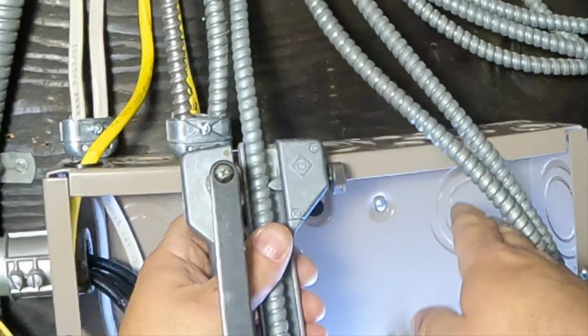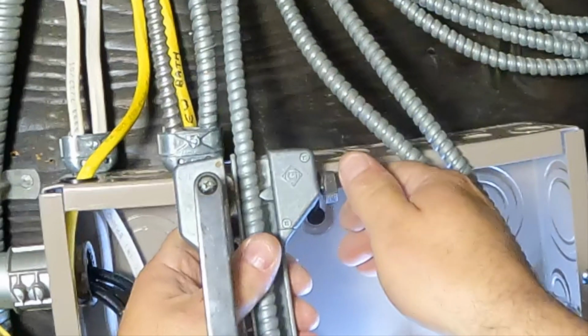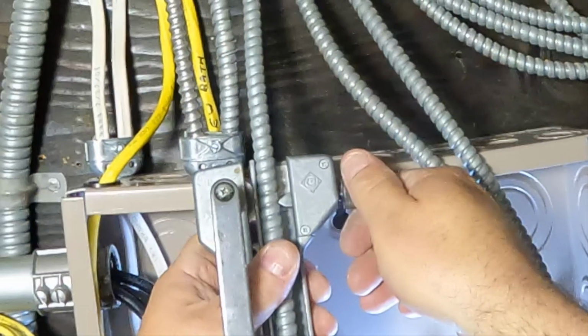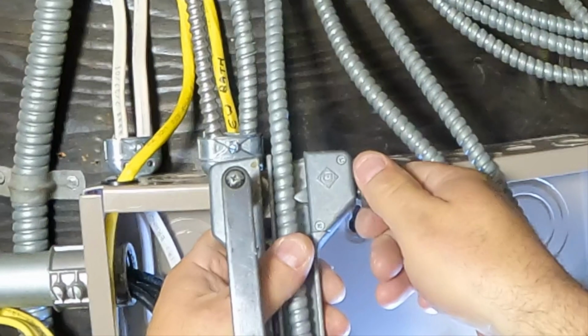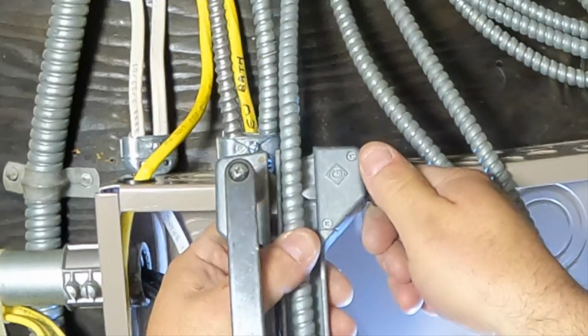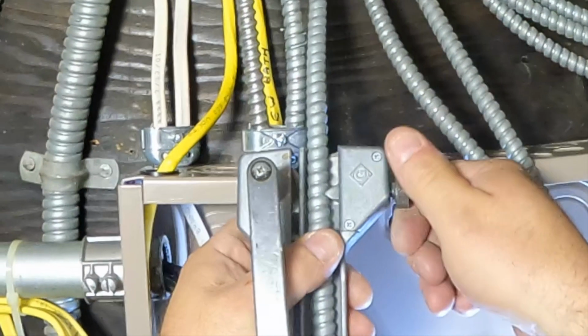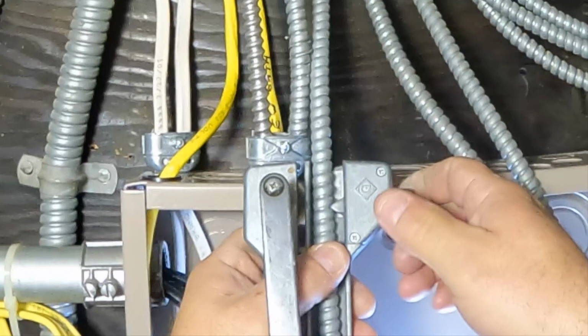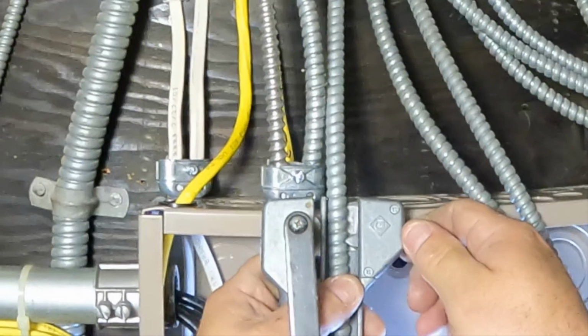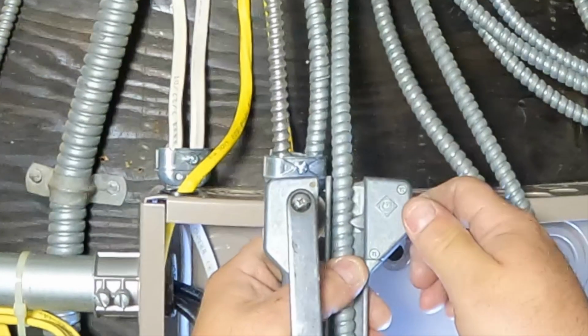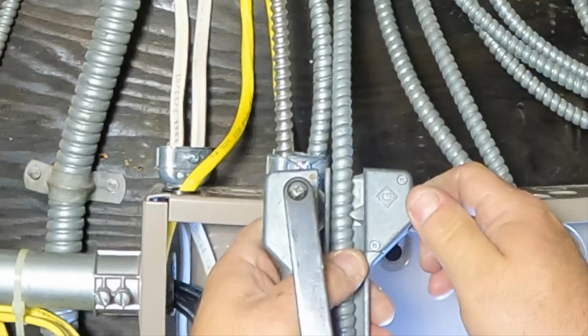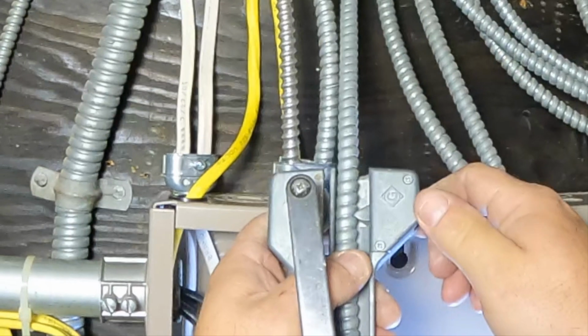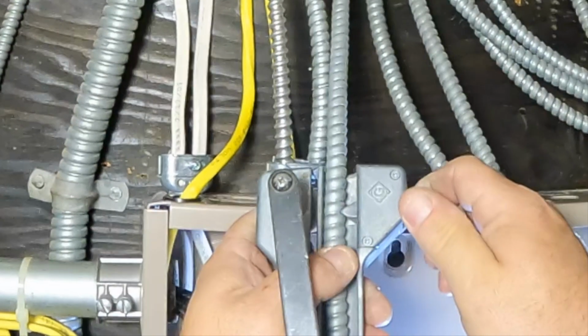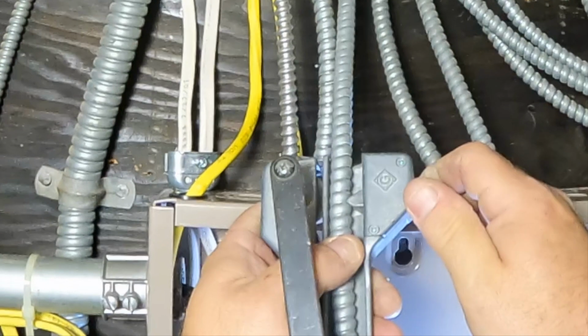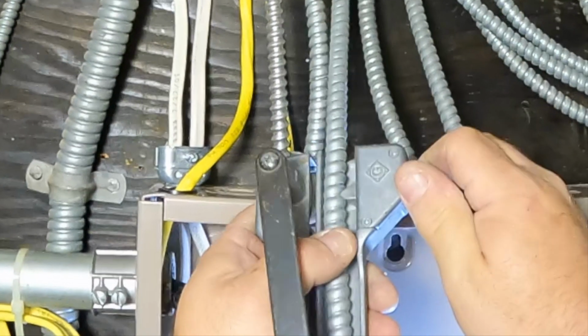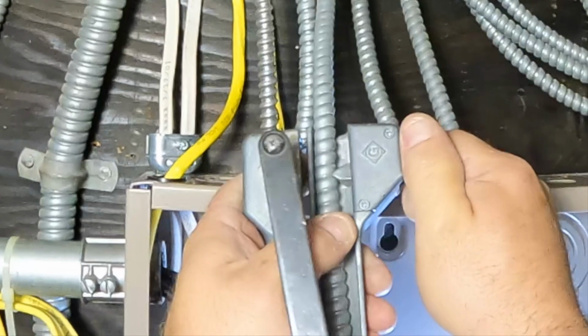Okay, so if you're here and you're not an electrician, or maybe you're an electrician just getting started, this is how you use the BX cutters right here. You put the cable inside this little tray, and as you can see, I have a knob that I'm tightening down with my right hand. I'm tightening that down, that little tooth that sticks in there. Tighten it down until it's firm, and then you're going to grab the crank and hold the cable in there and crank it before breaking the seal on the sheathing. And that's how you strip a piece of BX.